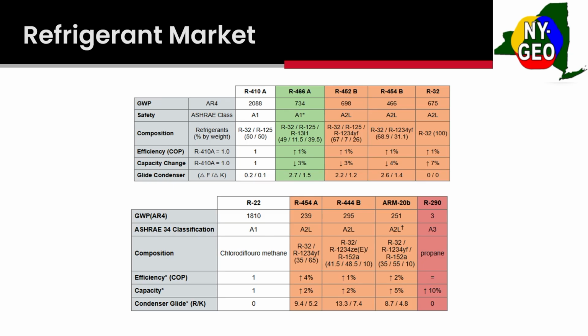But in order to really get our arms around this, we need to start getting comfortable working around flammable refrigerants. And the A2L is a good start for that. What that means is no torches or open flames around the equipment, sparkless motors, so your fan motors, vacuum pumps, stuff like that, meeting ventilation requirements. That is a big thing with VRF. And with R290, right now with ASHRAE, there are strict charge limitations, so you can have no more than 150 grams of R290 per circuit. So that really limits what you can use right now and how you can design equipment. Another big thing, the R290 propane, it's not the same propane you have in your backyard with your barbecue grill.